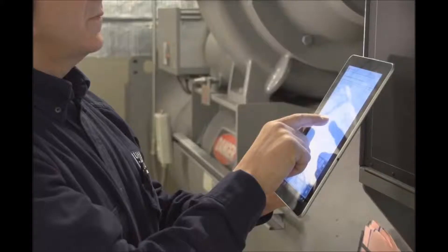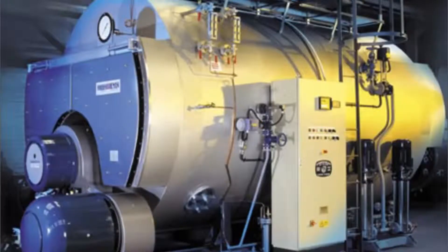Next, we visit the site. We examine all significant processes. We will ask: how well controlled are they? Are they best practice? Is there any waste? Is the equipment too large for the job? How do others in the industry do it? And what should be the target energy consumption?